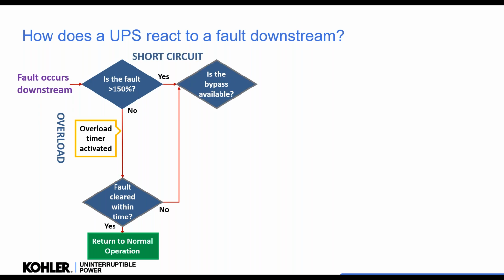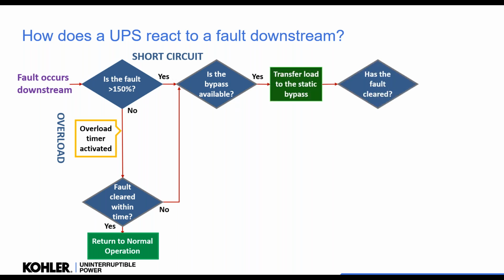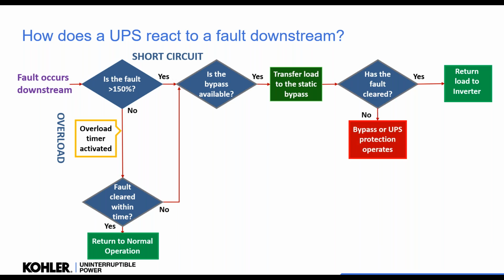If it doesn't, it treats it the same as a short circuit, and it asks, is the bypass available? Is the mains available? Because if it is, that's much more powerful than the inverter. Let's go to bypass, use that to trip the downstream protective device, and hopefully return back to load on inverter after that's done. Now, if it still can't clear the fault using the mains, something has to give. So either the bypass protection in the UPS or the upstream protection needs to clear to make things safe.